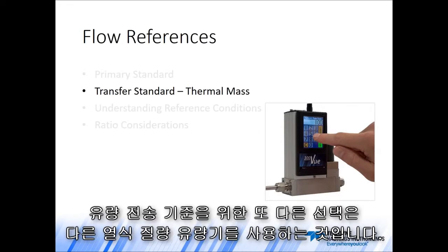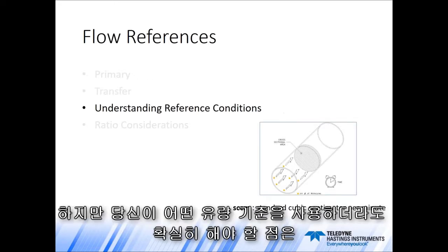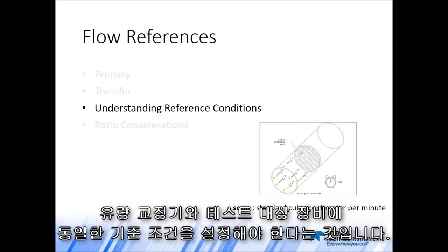Another choice for a flow transfer standard is to just use another thermal mass flow device. These are generally going to be far less expensive, and in many cases will provide the required accuracy. But whatever flow standard you're going to use, make sure that you decide upon the reference conditions that are being used both by your flow reference and the unit under test.